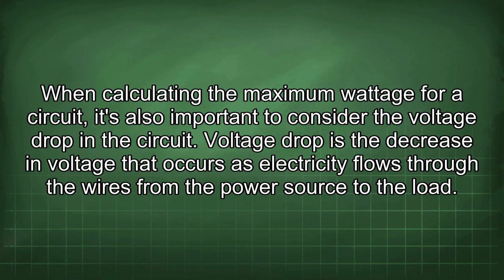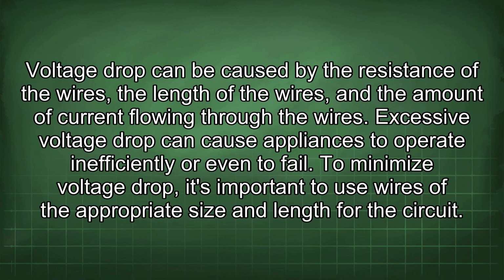When calculating the maximum wattage for a circuit, it's also important to consider the voltage drop in the circuit. Voltage drop is the decrease in voltage that occurs as electricity flows through the wires from the power source to the load. Voltage drop can be caused by the resistance of the wires, the length of the wires, and the amount of current flowing through the wires. Excessive voltage drop can cause appliances to operate inefficiently or even to fail.